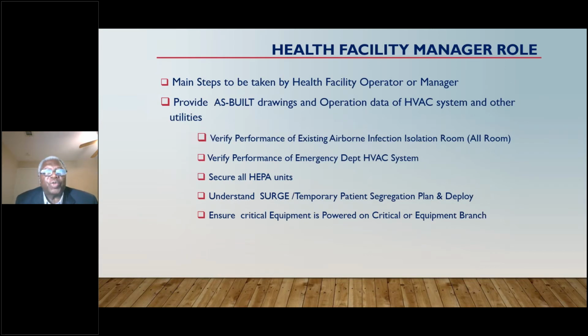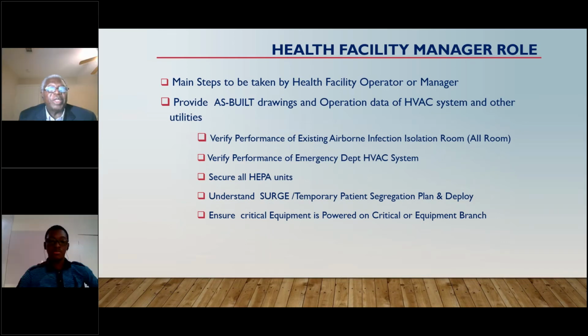Health facility manager's role: the main steps to be taken by the health facility operator or manager are as follows. They must be able to immediately provide as-built drawings as well as operational data of the HVAC system and other utilities. They must also verify performance of existing airborne infection isolation rooms, verify performance of the emergency department HVAC system, and secure all HEPA filter units, keeping them safe.